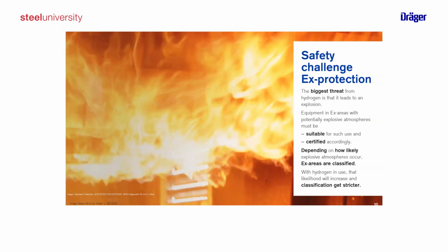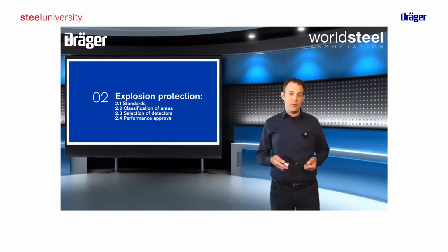But, and here we come again to the challenge, hydrogen is a very explosive gas, and there are some topics about hydrogen you have to be aware of. The main threat is the explosiveness of this gas. Related to this, we have a lot of topics about suitable equipment that must be certified. We are talking about Ex areas and the classification. Also standards and regulation will get stricter and stricter. That at least is what we currently see on the market. And this is now the part where I would like to hand over to Marcus, and then we will come back to more insight regarding explosive atmospheres.